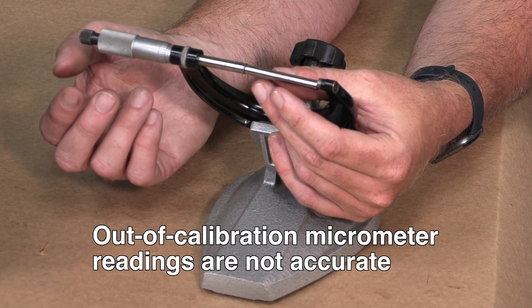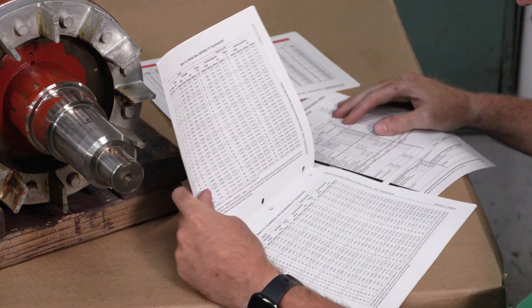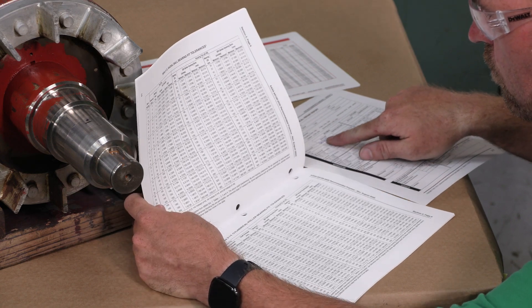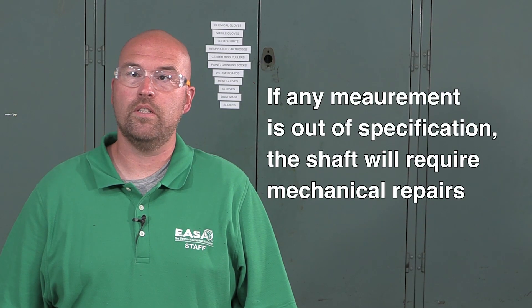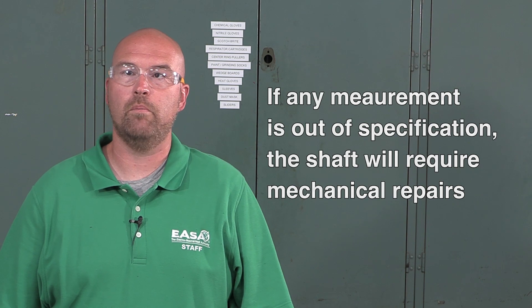If the micrometer is out of calibration after taking your journal measurements, then those measurements are considered inaccurate and must be repeated with a calibrated micrometer. The final step is to verify that the journal dimensions measured with the calibrated micrometer correspond with those in the ANSI/EASA AR100 standard. If any measurement is out of specification, the shaft will require mechanical repairs to ensure proper bearing fitment.